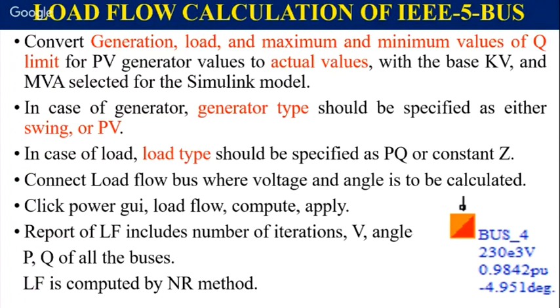Then in case of load, we have to connect all this. That is why I have mentioned it here. You have to mention that in every respective block. In case of load, you have to mention whether it is PQ or constant Z. Then connect the load flow bus where voltage and angle are to be calculated. This orange color bus is shown. When you connect it in the model, this will give the indication that you have to calculate the load flow at this particular point. And once the load flow is calculated, this 0.9842 is the voltage after load flow calculation, and this is the angle at which this voltage is there. So it is given. This is the location.